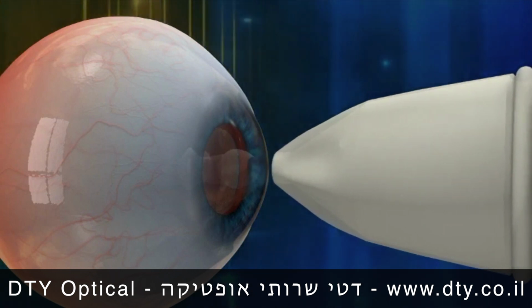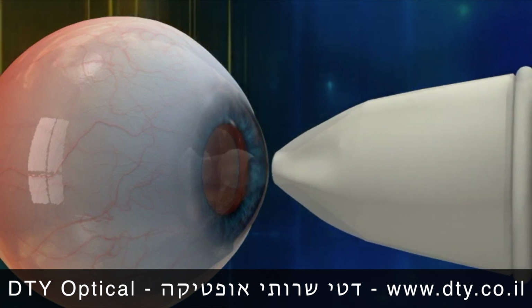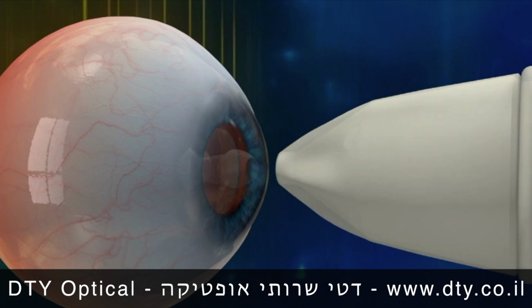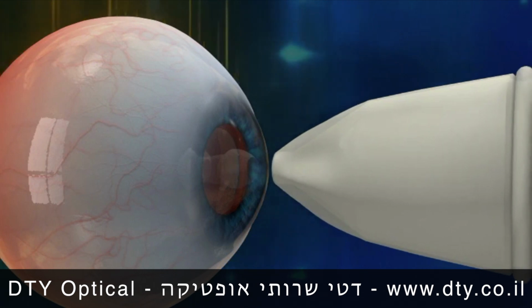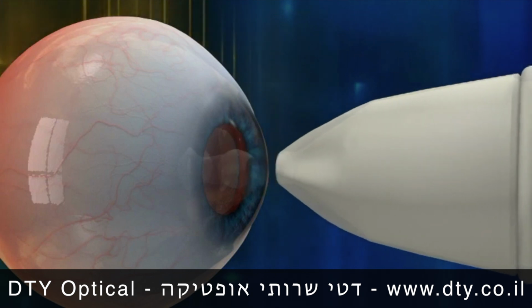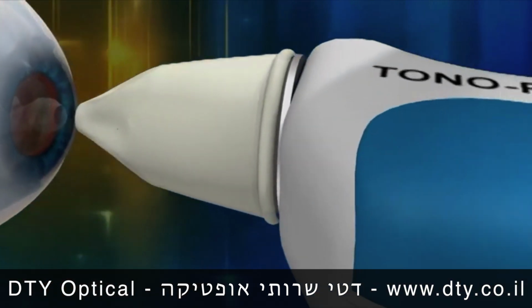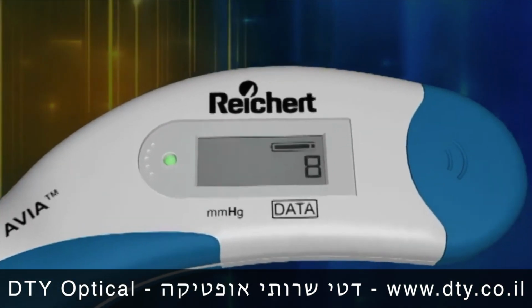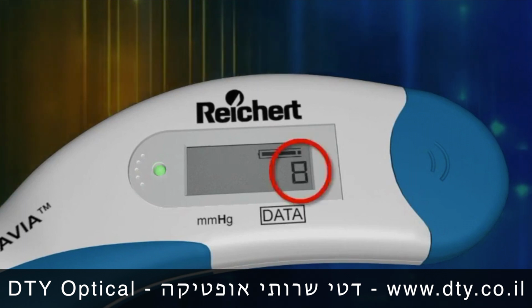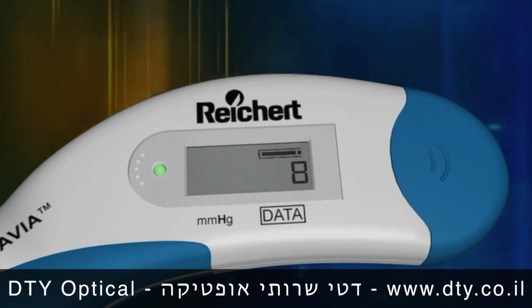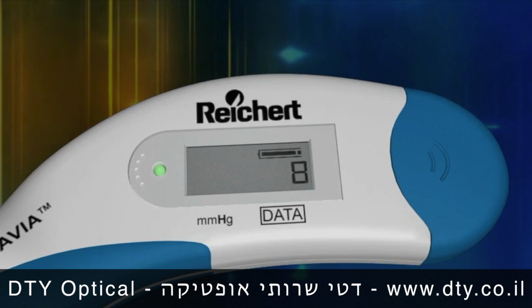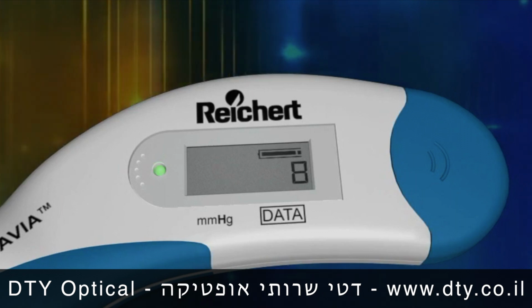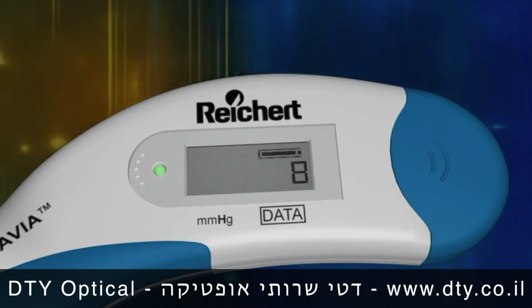You will hear a click sound with each applanation. With ideal technique, you will hear 2 clicks for each touch of the eye, signaling that a reading was taken on both the inward applanation and outward applanation. The data field of the LCD registers the number of readings obtained. The Tonopen Avia tonometer takes 10 readings and displays the average.